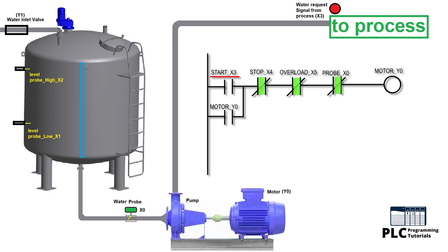As you can see, we have a start push button x3 and stop push button x4. Stop push button is used as normal close contact. Motor overload signal x5 and water probe signal x0 both are used as normal close contacts to stop the pump in case the motor is overloaded or there's no water in the pump suction line.